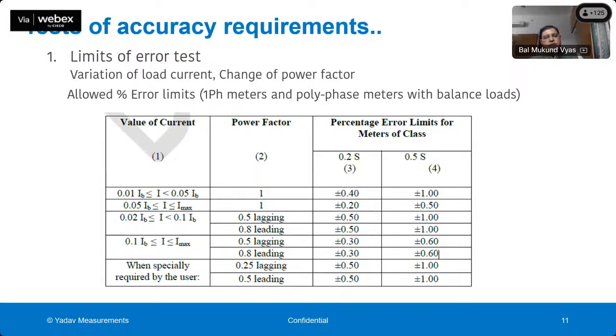So let us see all these tests in slightly more detail. The first test is the limits of error test. You can see the current is being varied, and when current is varying, the power factor also is specified differently in the standard, and there are limits specified for different values of current and different values of power factor.